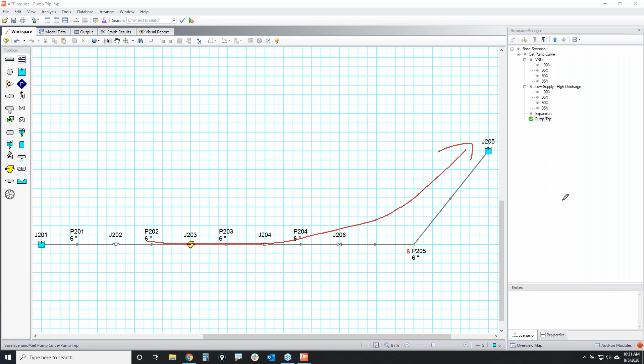So let's say that you want to do some pump transient modeling. This is a system where I'm pumping water up a hill over an elevation change of about 200 feet. And initially the pump is operating at steady state just fine, 500 gallons per minute. Here's what my pump curve looks like. I have an NPSH curve and an efficiency curve.